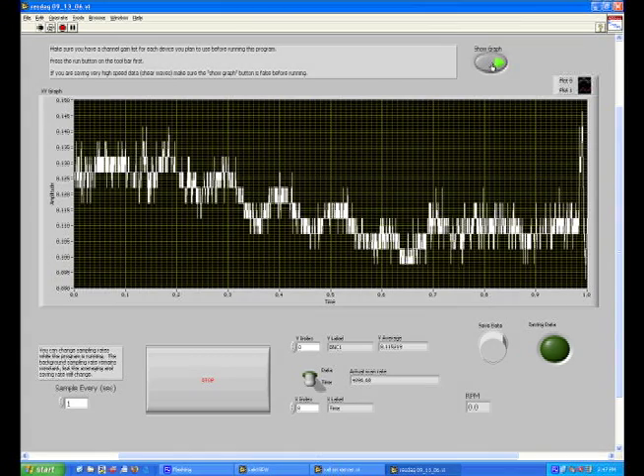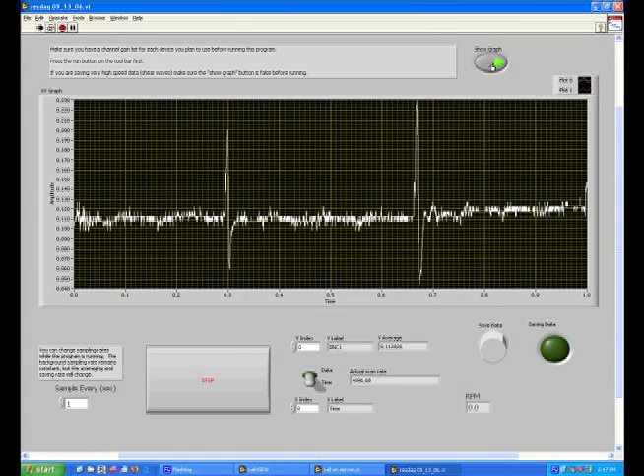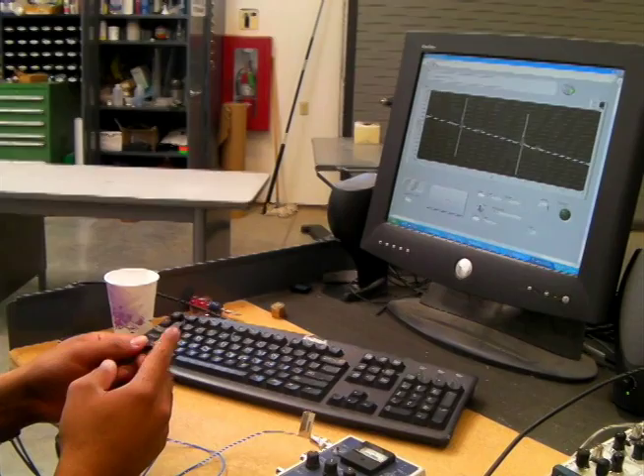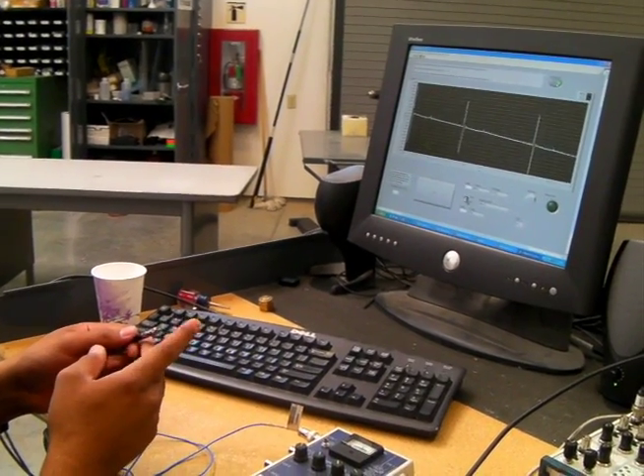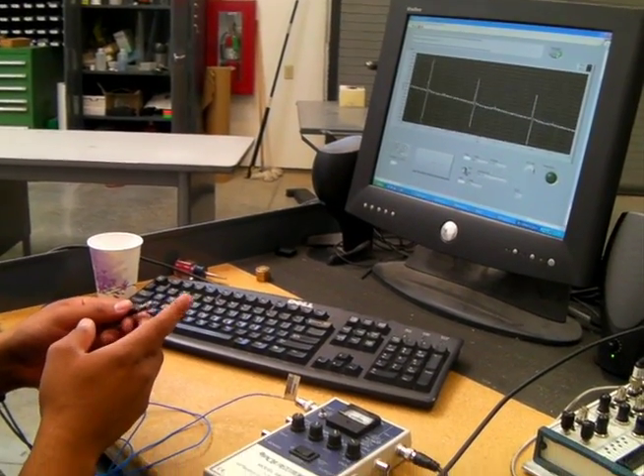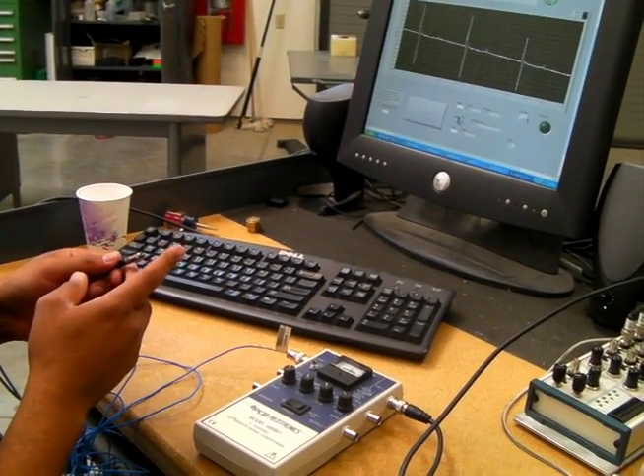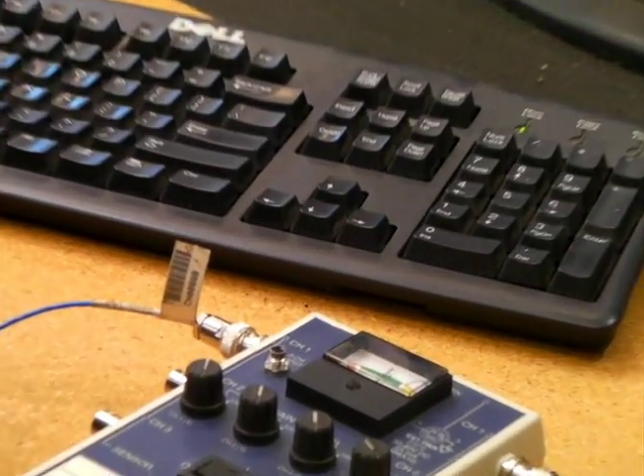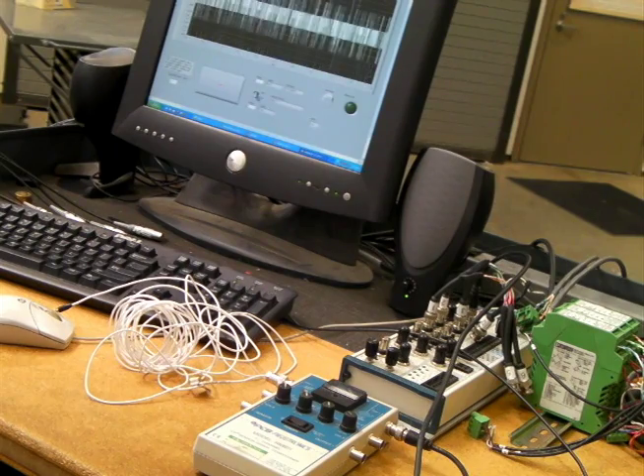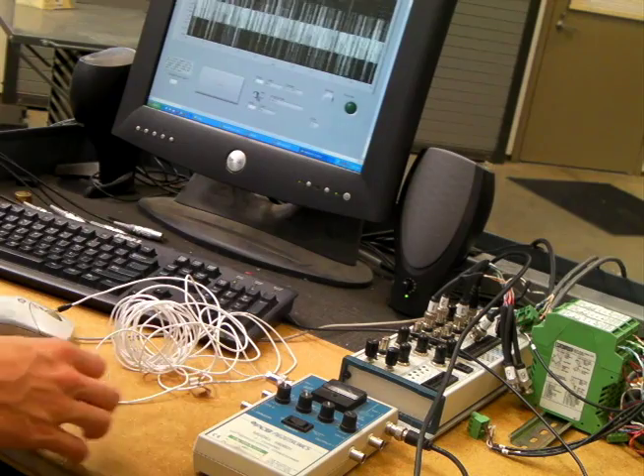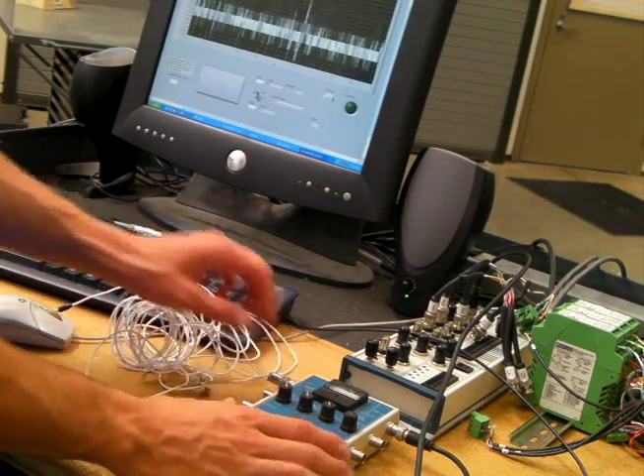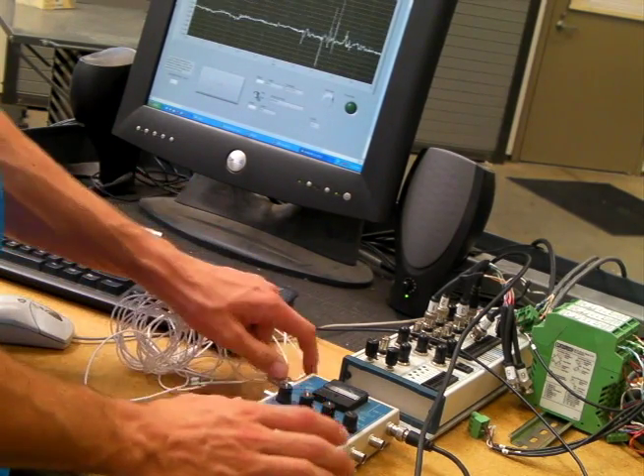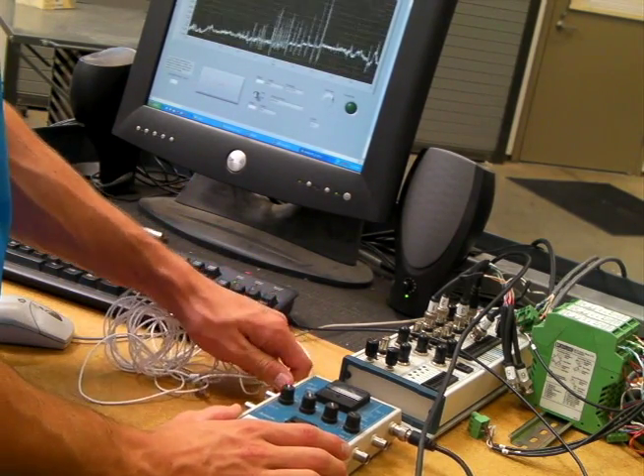You may then test your accelerometer by gently tapping on it to verify a spike in the graph for each tap. If your tapping does not yield a signal then there is something wrong. The problem could stem from a number of issues including a broken accelerometer, improper setup of ResDAQ, or improper setup of inputs.